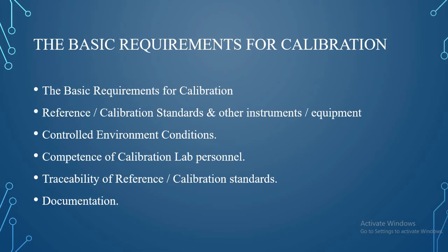Now here, what are the basic requirements for calibration? The basic requirements for the calibration are reference or calibration standards and other instruments and equipment. So when we calibrate any equipment or instrument, we have to refer to some standard value, or we have to compare the reading of that instrument with another calibrated instrument. And by comparing the results of both instruments, we can calibrate the equipment or instrument.